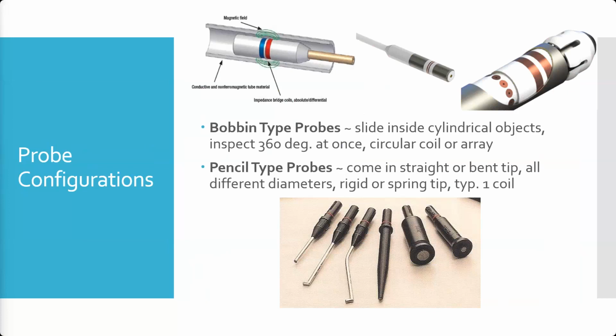Or these are big coils, these are little coils. These are finding cracks on the inside of the tube. These are looking at corrosion on the outside of the tube. Say you have a pipe that runs underground, and you want to make sure that the inside is in good condition and that you aren't getting, particularly with steel pipes used in gas and oil, corrosion forming from the wet soil being around the outside of the pipe, without having to dig the entire pipe up and inspect it manually. They may use something like this.